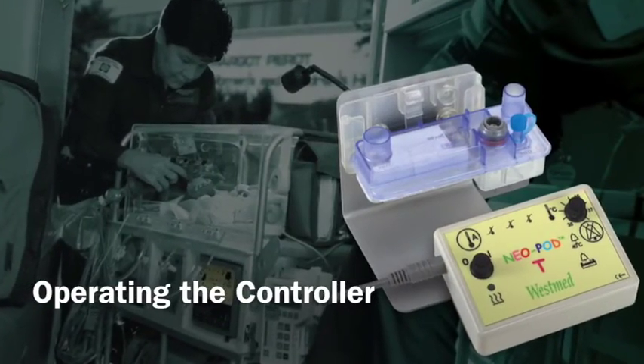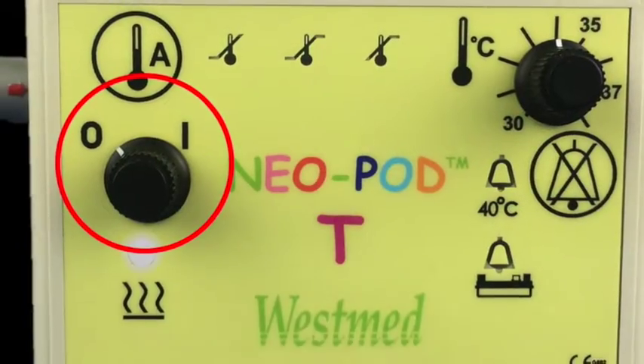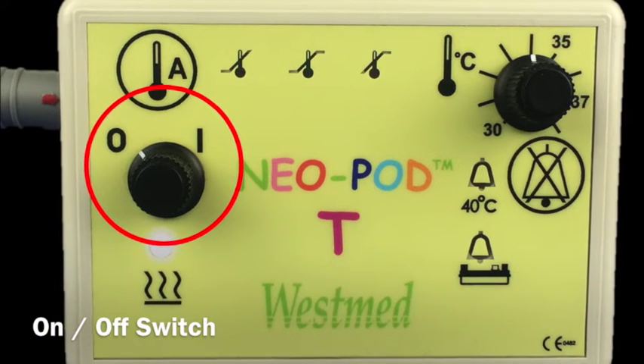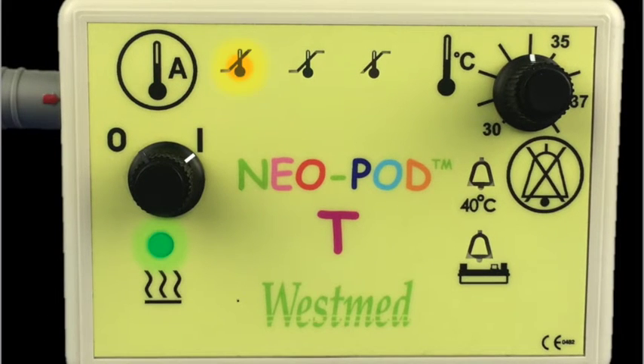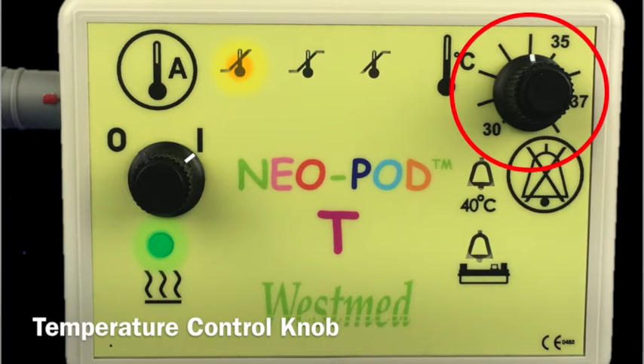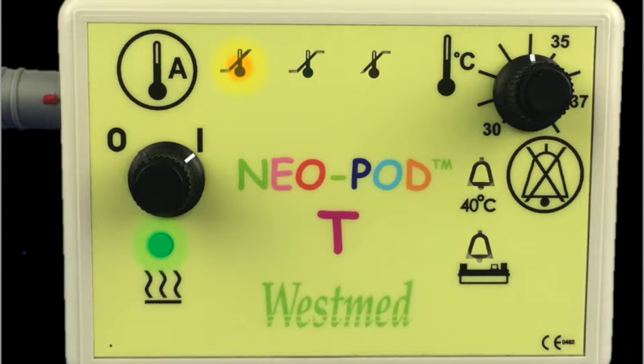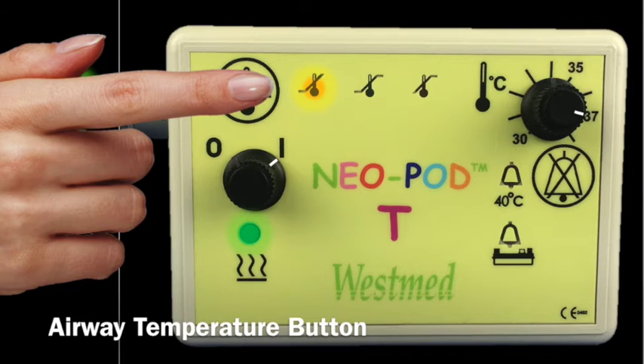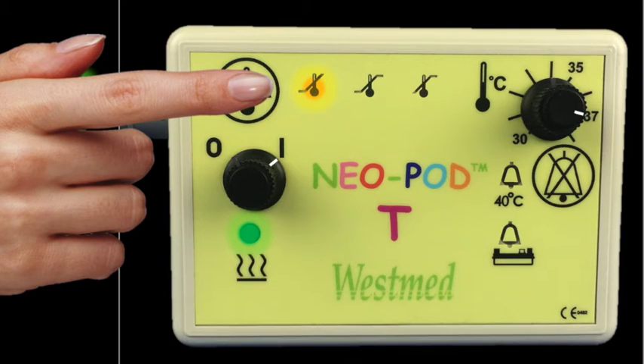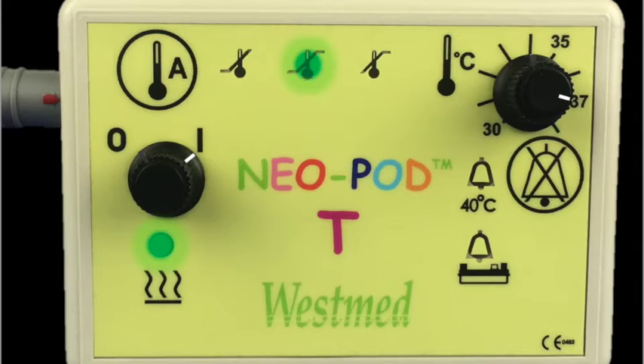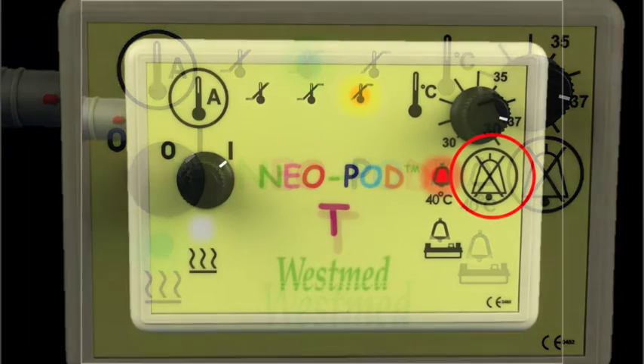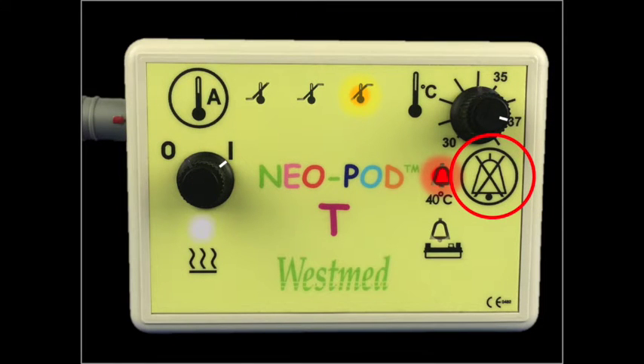Operating the control unit of the Neopod T. The Neopod T control unit has an on-off switch which turns the power on or off to both the Neopod T and the LavaBed cartridge. The temperature control knob sets the temperature of gas required at the LavaBed outlet port. The airway temperature button, when pushed and held, displays the airway sensor probe status. When released, the control unit will continue to display the LavaBed outlet status. The alarm silence button will silence the audible alarm for 90 seconds.